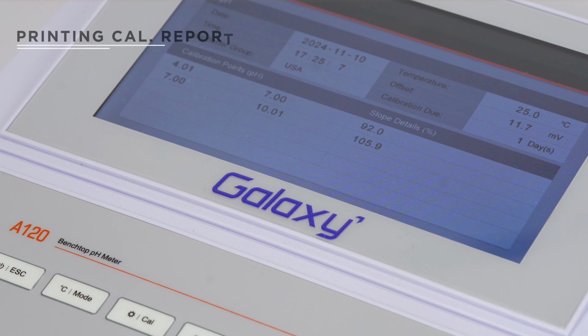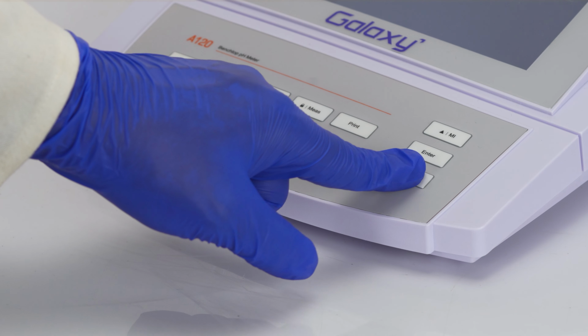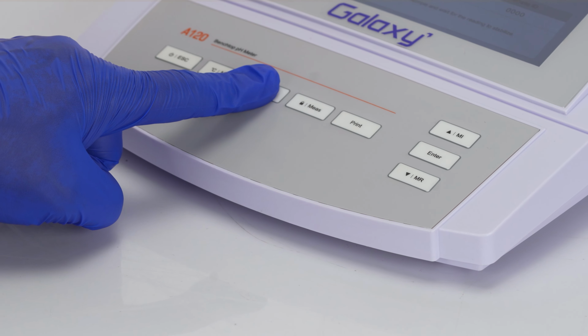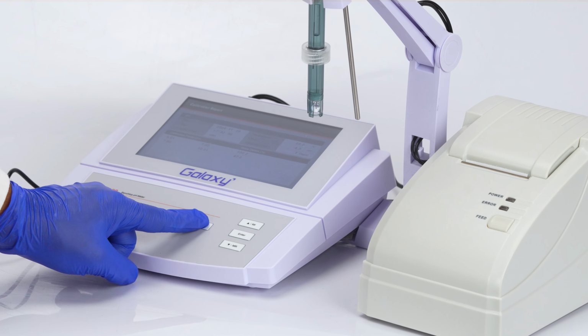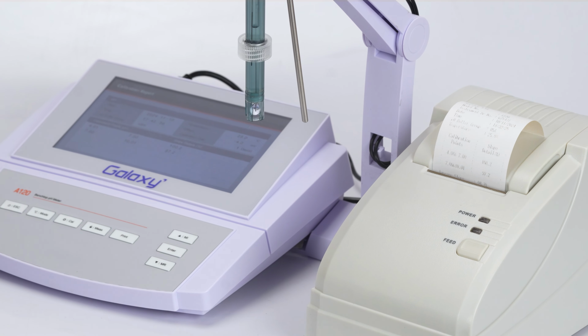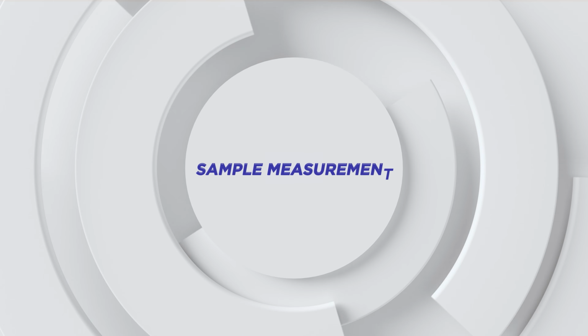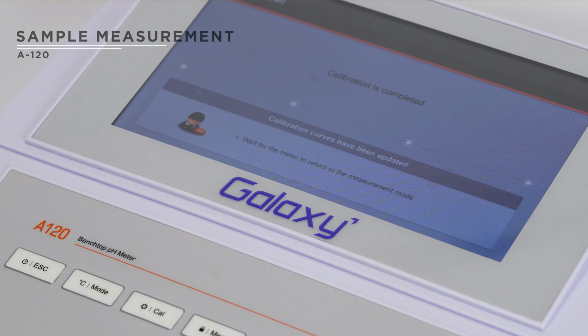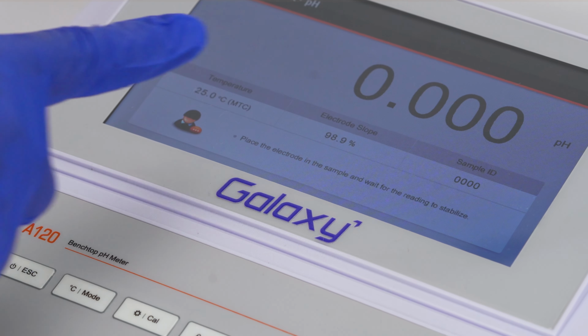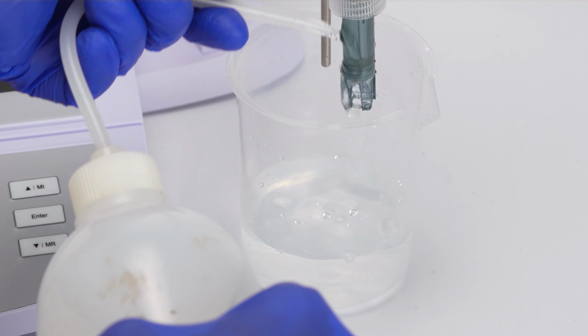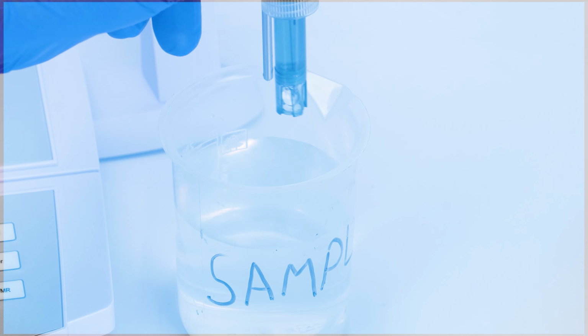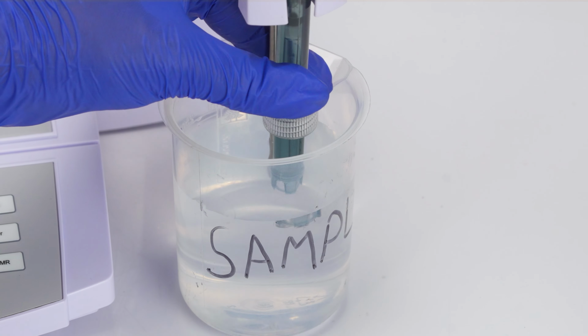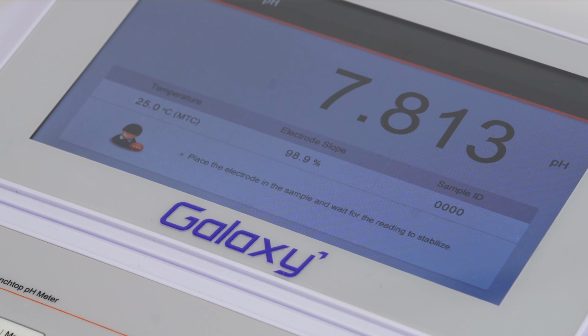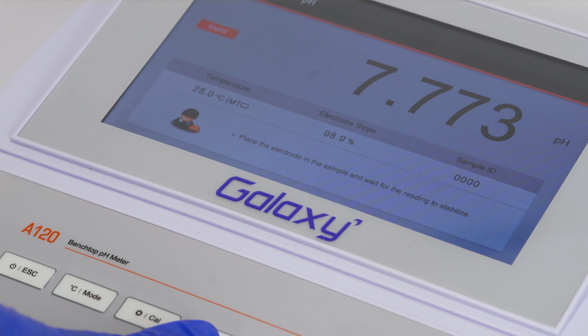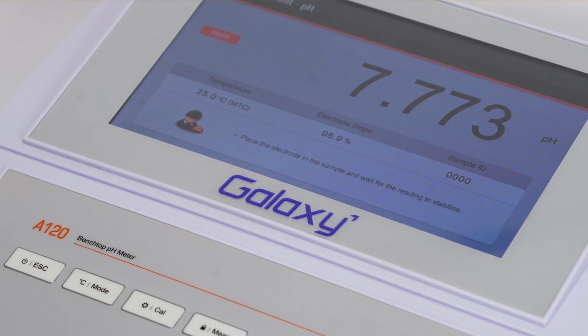You can print the calibration report: press the MR key, go to the calibration report, press enter, then click the print option. It will print your data like this. With the calibration complete, you are now ready to measure your sample. Rinse the electrode again. Place it into your solution and gently stir for an accurate reading. Wait for the stable icon to appear on the screen, which ensures the reading is precise.